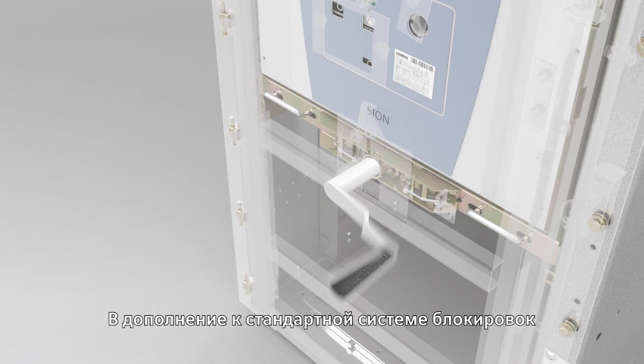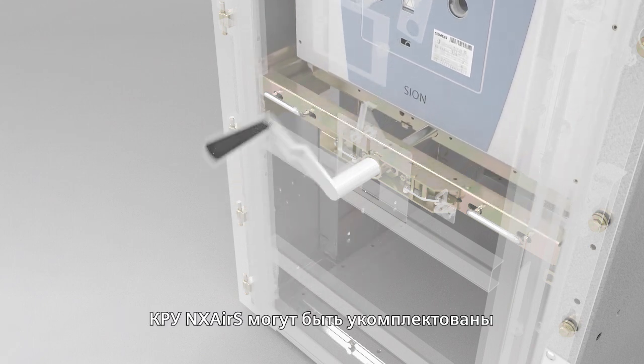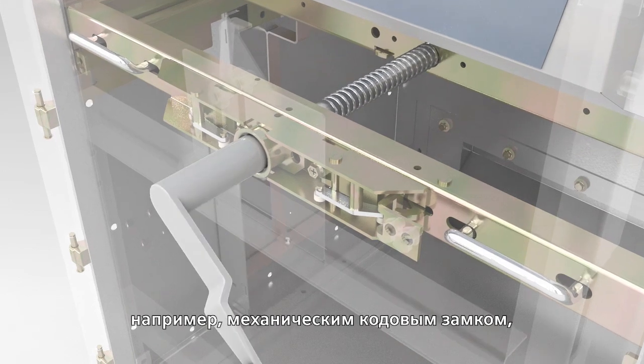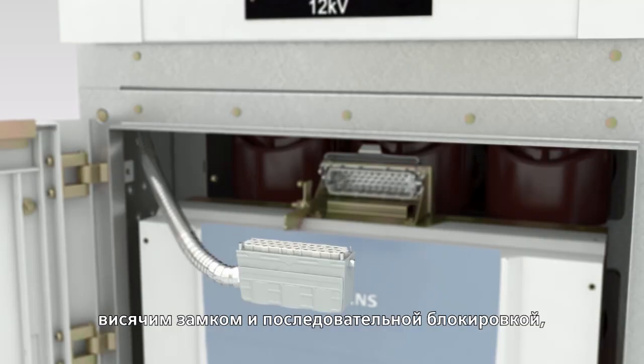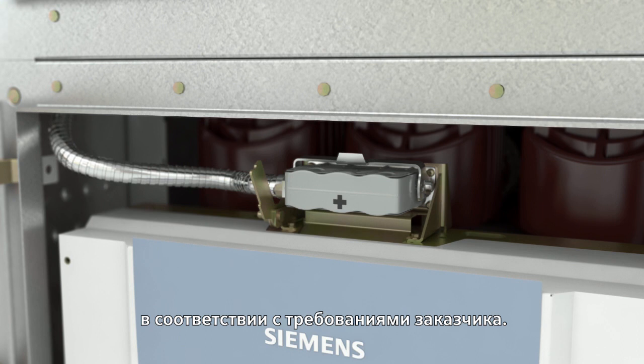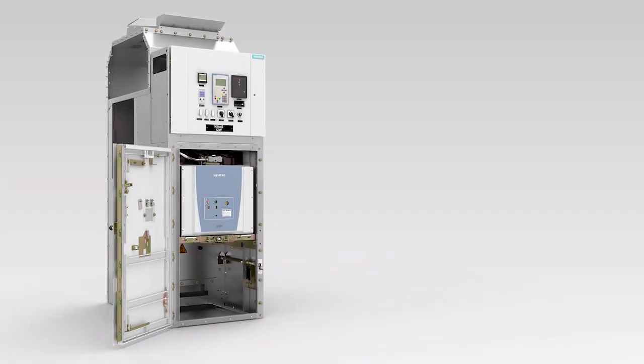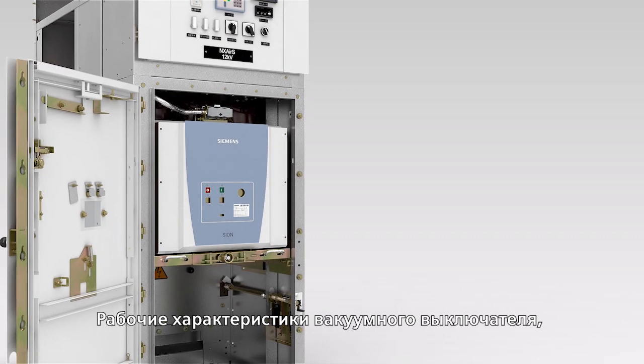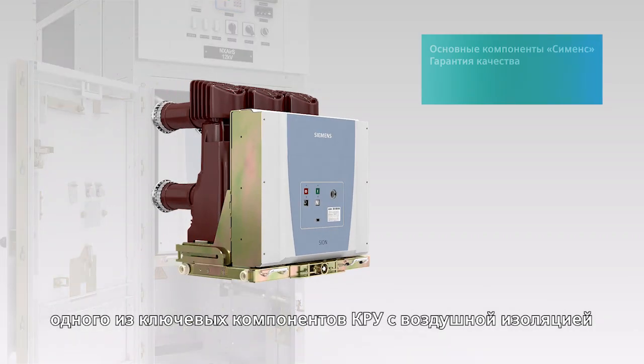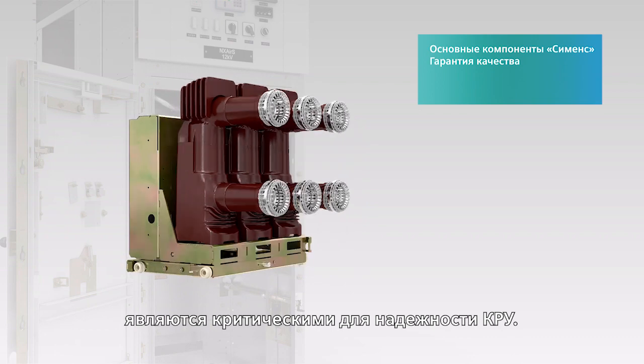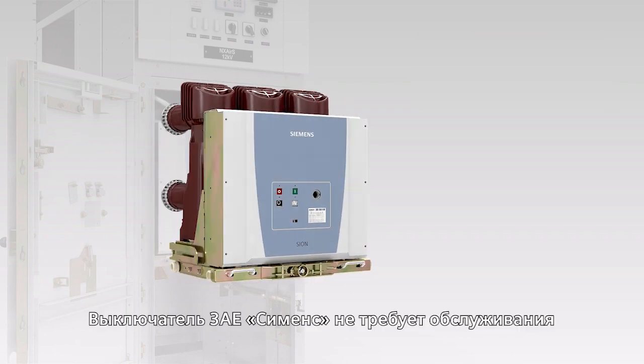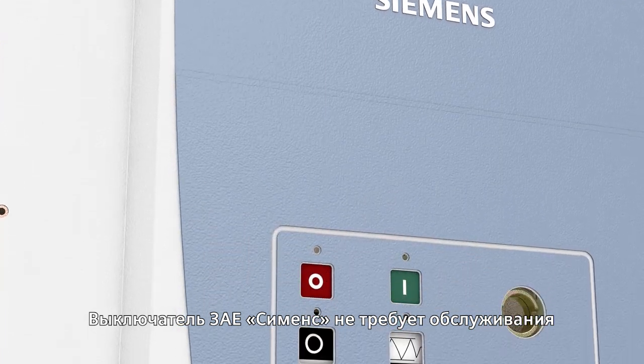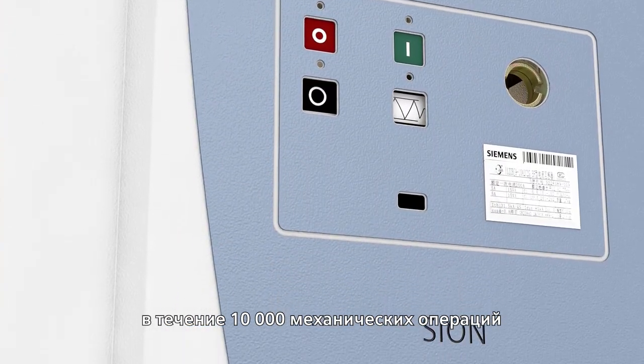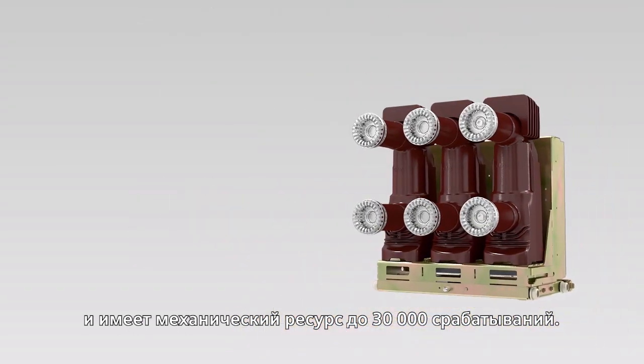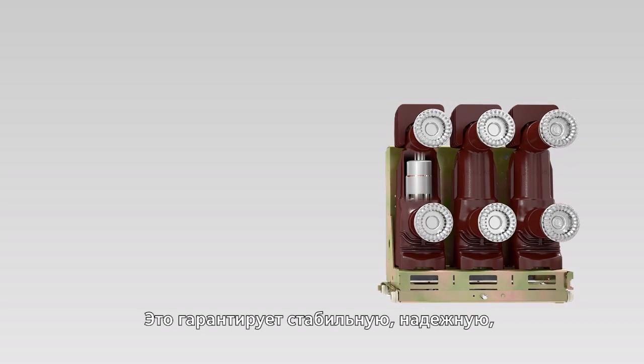Besides this standard interlocking system, NXAirS switchgear has optional interlocking functions such as mechanical code lock, padlock, and procedure lock according to customers' requirements. As one of the core components of the air-insulated switchgear, the performance of the vacuum circuit breaker is crucial for the reliability of the switchgear. The Siemens 3AE circuit breaker is maintenance-free for 10,000 mechanical operations and reaches a mechanical life up to 30,000 times. This guarantees stable, durable, and safe operation.